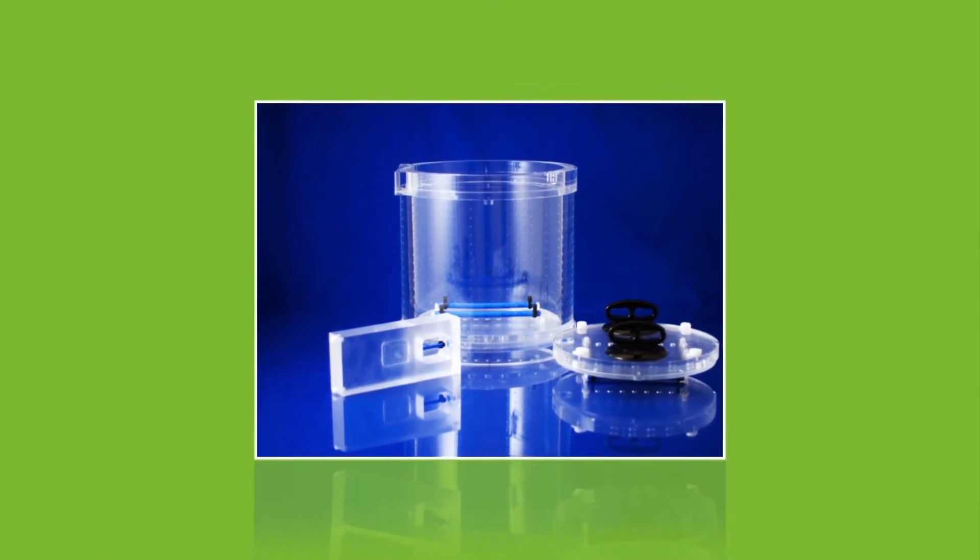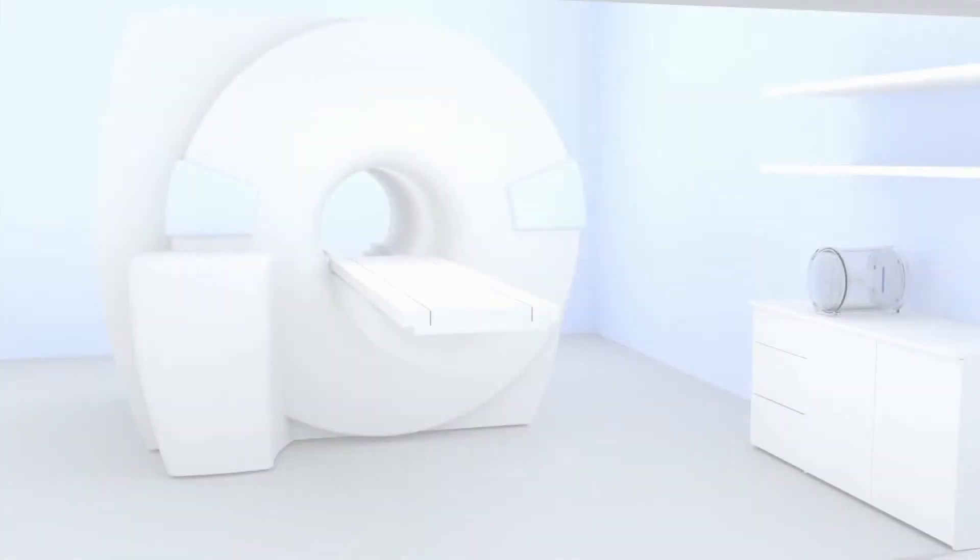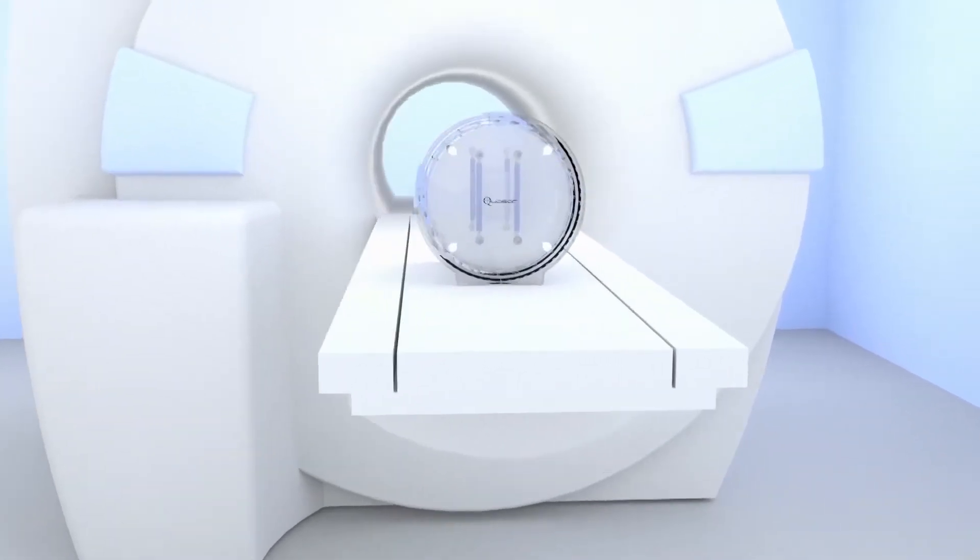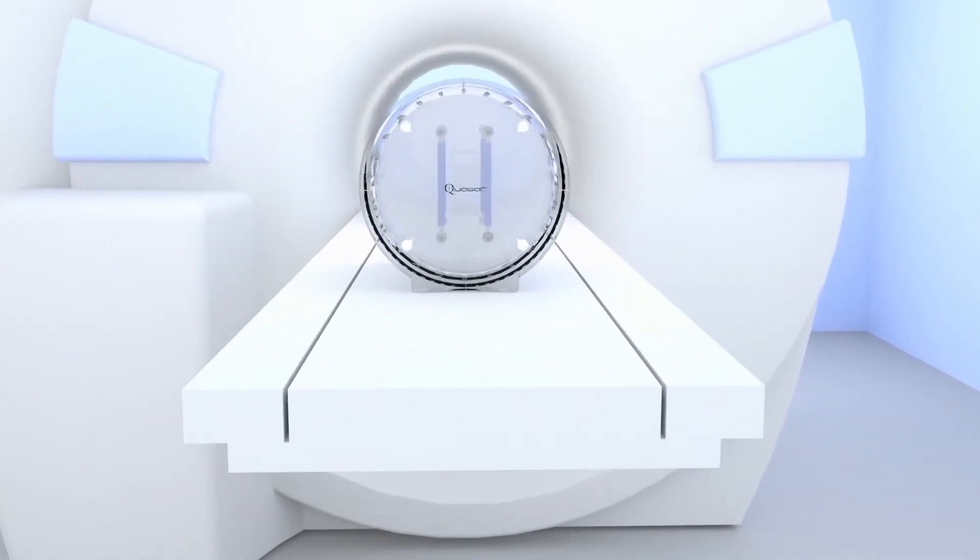At 21 kilograms, the large-volume phantom is half the weight of conventional solid fluid-filled grid phantoms for easier and faster setup.